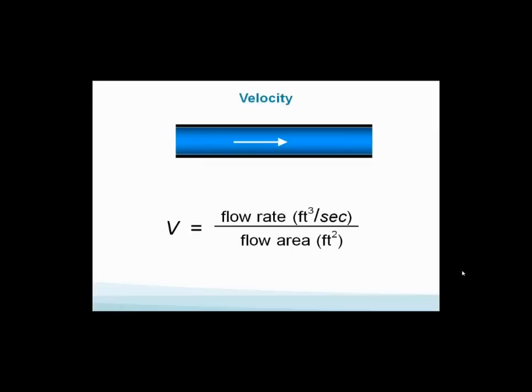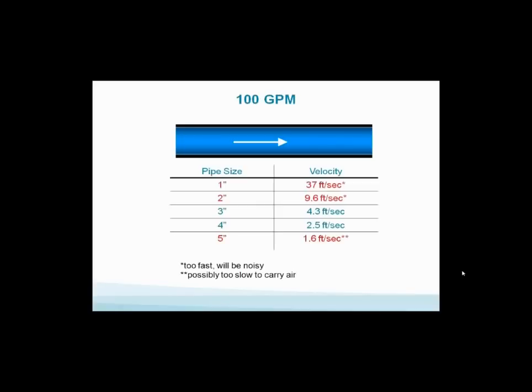So how about velocity? Pretty straightforward equation, but you need to look at velocity because velocity has a lot to do with how you handle the air. If you get velocities too high, your piping will be noisy. So let's take a look.